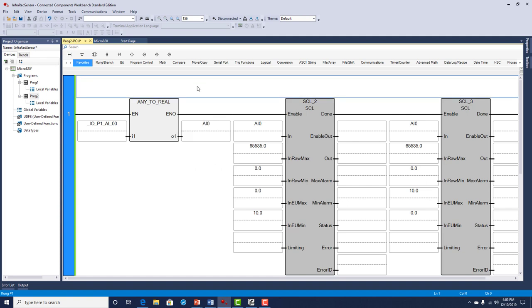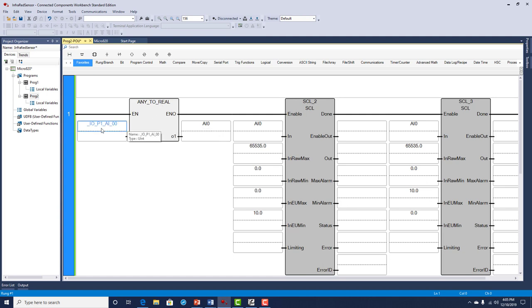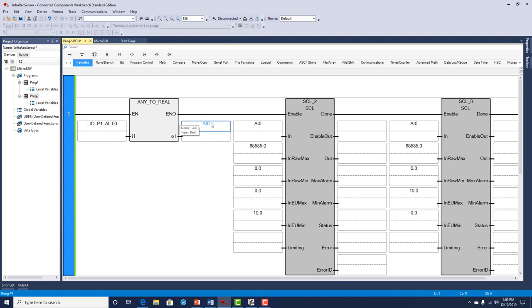This instruction is an any to real. It will convert any data type to a real data type. The reason we have to do that is because the SCL scale instruction does not accept anything but floating point. And our analog input is an unsigned integer. So the very first instruction we convert that analog input. Notice P1 that means plug-in module. If it was an embedded analog input it would say EM. So I'm taking my analog input that I have that sensor hooked up to and I convert it to a real data type that I named analog input 0.